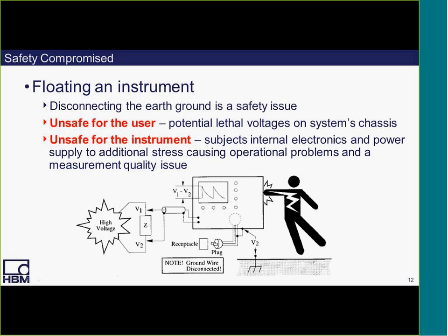Well, we've all probably floated an instrument at least once in our lifetime. Actually, before floating the instrument many years ago while in college, I was designing an AC regulator circuit, and immediately after attempting to measure the AC output with a scope probe, I saw a spark and tripped the breaker because I shorted the AC output to ground. So then I decided to float the instrument and didn't realize there were lethal voltages on the case of the instrument. And unfortunately, I still see from time to time people floating an instrument in order to make a high voltage measurement by disconnecting the earth ground of the measuring device.